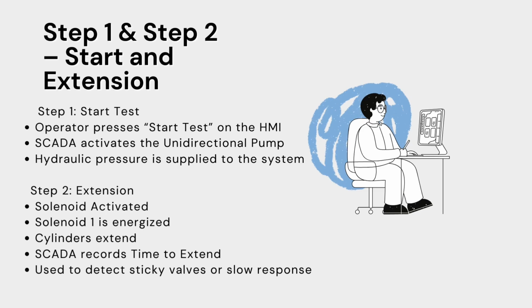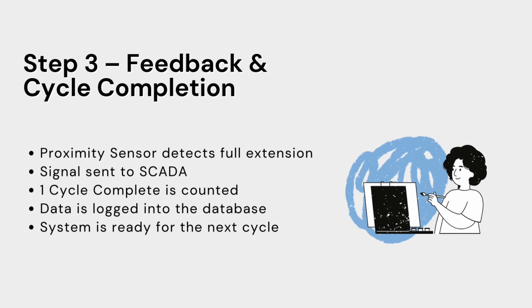As for the second slide, which is step 1 and step 2 of the system, the start and extension. The test begins when the operator presses the start test button on the HMI. This sends a signal to SCADA, which starts the unidirectional pump. Next, solenoid 1 is activated, which allows the hydraulic fluid to extend the cylinders. During this movement, the system measures the time taken to extend, which helps detect issues such as sticky valves or flow restrictions.